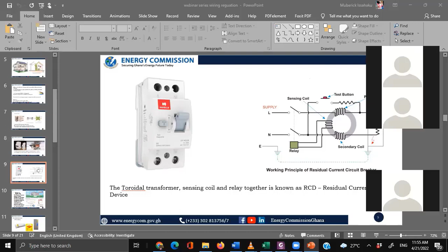So the comparison here is, if one electromagnetic field is generated above the other, and more often it happens when it's coming from the neutral, that means the magnitude of current that was entering the RCD to the appliance is not the same as the magnitude of current that was coming out. And we know once there's power flowing, there will be some losses. But this RCD is designed such that the losses shouldn't exceed a certain degree. It varies from RCD to RCD. So, for example, if 5 amps is passing through the live and creates a magnetic field at the primary core, we should be expecting, ideally, that 5 amps will also be passing back through the secondary core, through your neutral. But we won't get it that way.